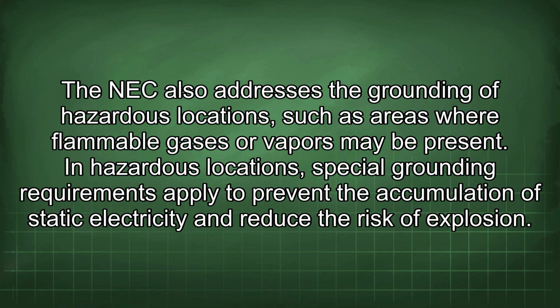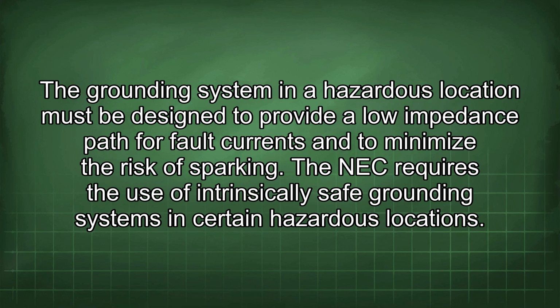The NEC also addresses the grounding of hazardous locations, such as areas where flammable gases or vapors may be present. In hazardous locations, special grounding requirements apply to prevent the accumulation of static electricity and reduce the risk of explosion. The grounding system in a hazardous location must be designed to provide a low impedance path for fault currents and to minimize the risk of sparking.